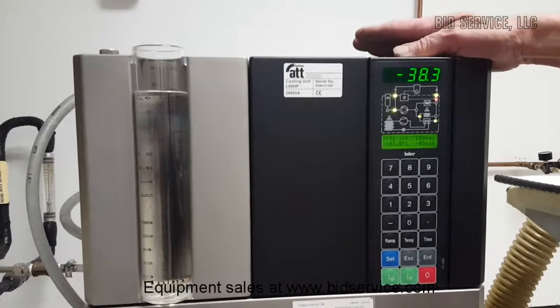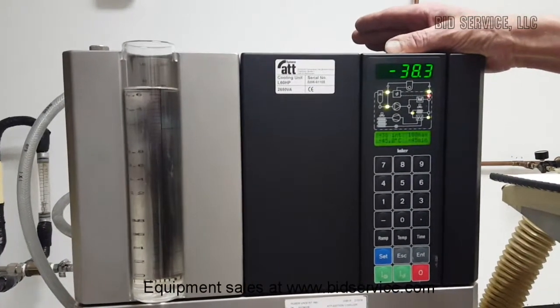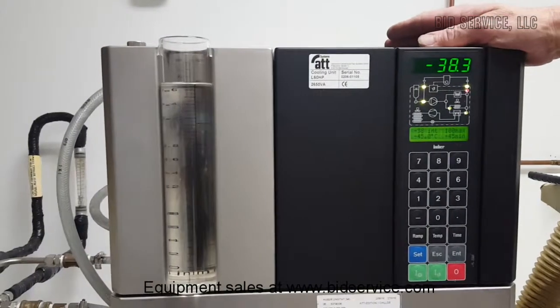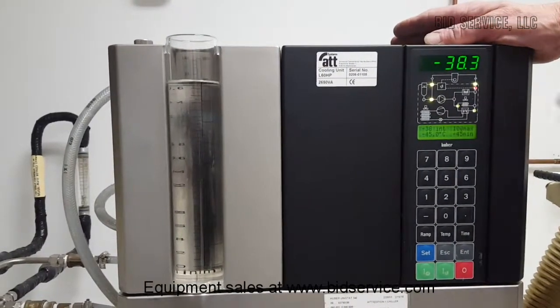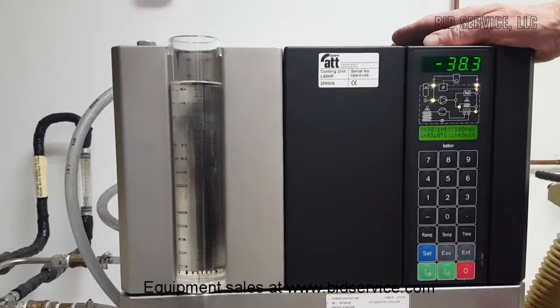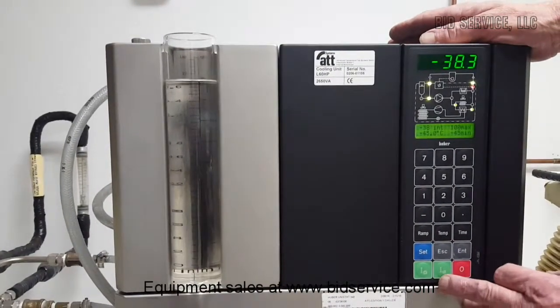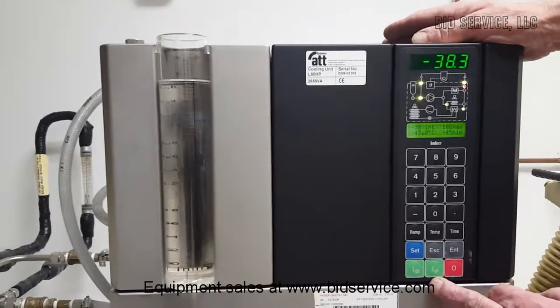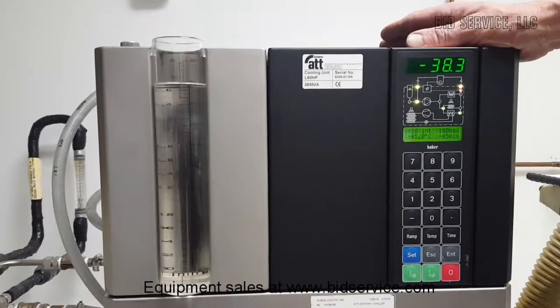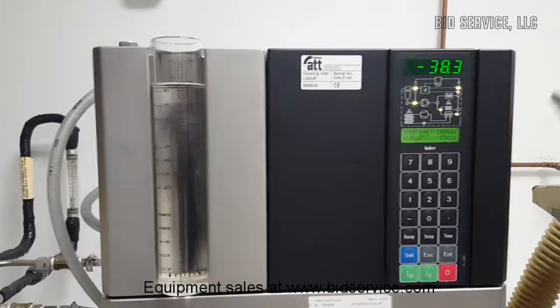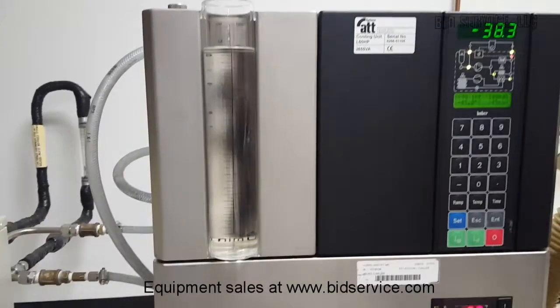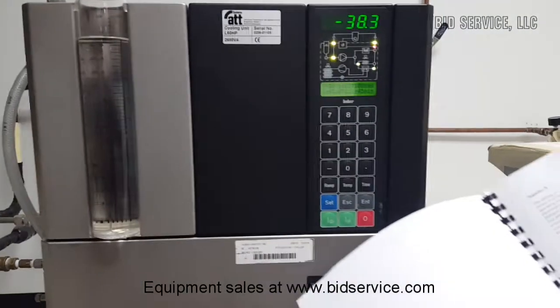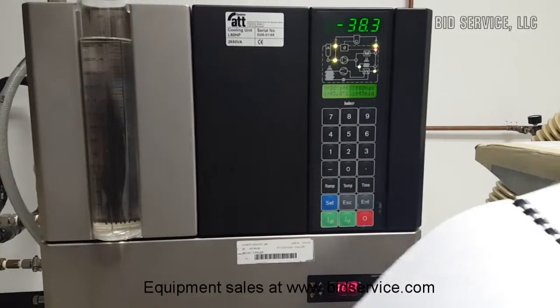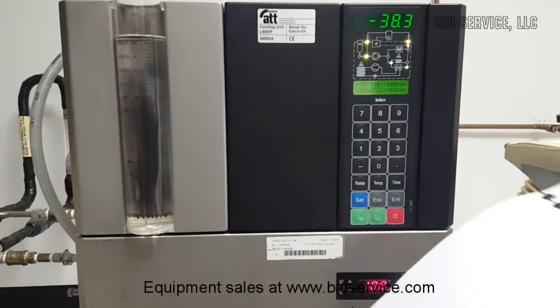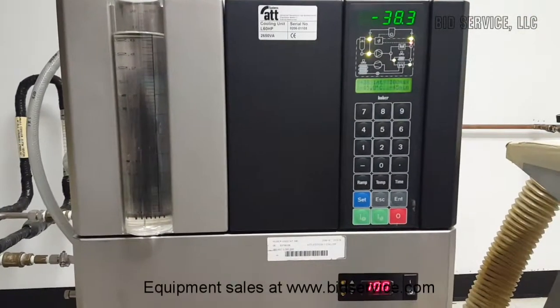This particular unit has been set for auto load. What auto load will do is after it boots up and it runs through its self-diagnostics, it will automatically start both the circulator and then the refrigeration compressor to achieve whatever your set points are. The actual setup of that for setting it from manual to auto load is well documented in the book here. It's pretty easy to follow. The program directory will tell you all the different programs that you can push to change the different parameters. Actually, this is one of the simpler controllers that I've worked on.